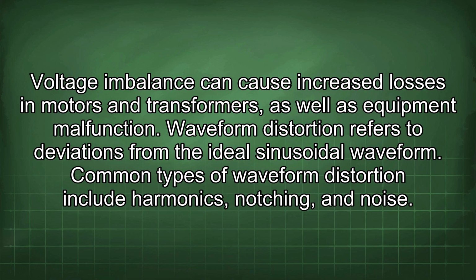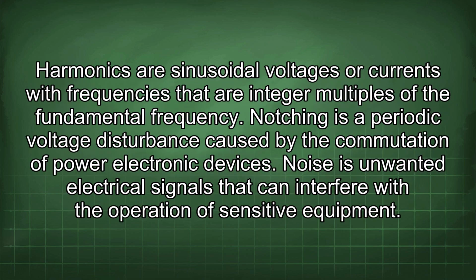Waveform distortion refers to deviations from the ideal sinusoidal waveform. Common types of waveform distortion include harmonics, notching, and noise. Harmonics are sinusoidal voltages or currents with frequencies that are integer multiples of the fundamental frequency. Notching is a periodic voltage disturbance caused by the commutation of power electronic devices. Noise is unwanted electrical signals that can interfere with the operation of sensitive equipment.